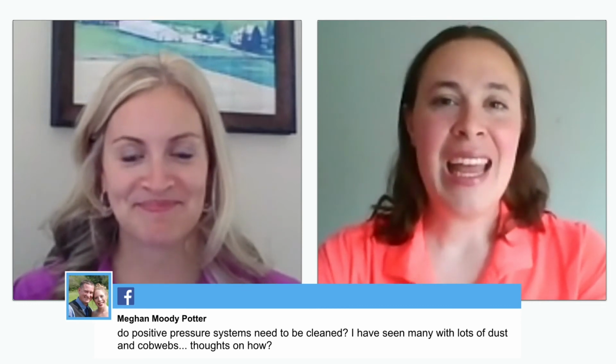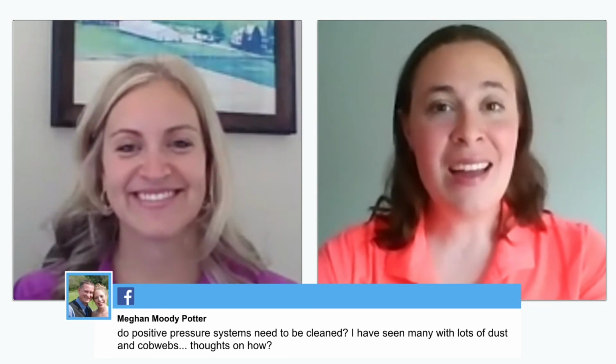A question we have from Megan Potter: do positive pressure ventilation systems need to be cleaned? I have seen many with lots of dust and cobwebs. Thoughts on how to clean them? Yes, good question, and yes, they should be cleaned. Most of the time there are clips where you can take the whole bag down pretty easily, as long as you have people who can go up on ladders and undo those clips. Some people will simply wash them down. Otherwise, they'll take a dusting mitt and dust the top, and then spray out the inside of the tube with water. A lot of times they'll hold the hose through some of the individual holes to concentrate on those really dirty spots.